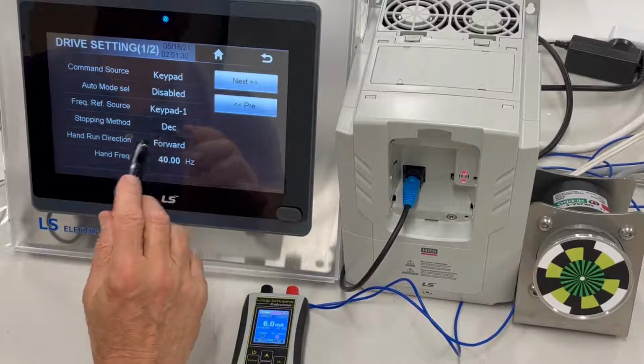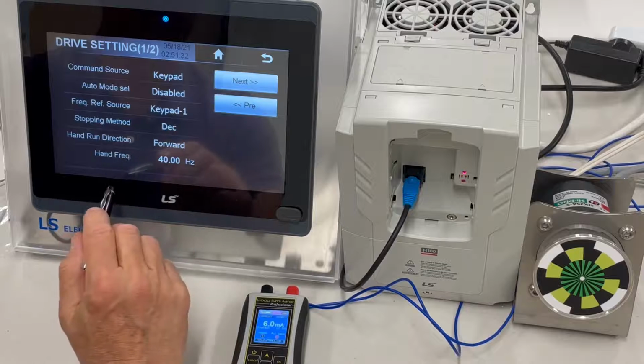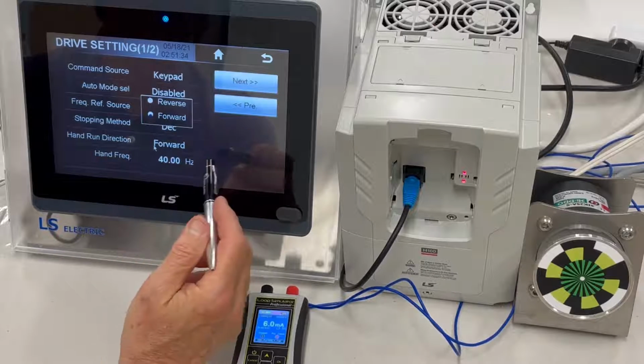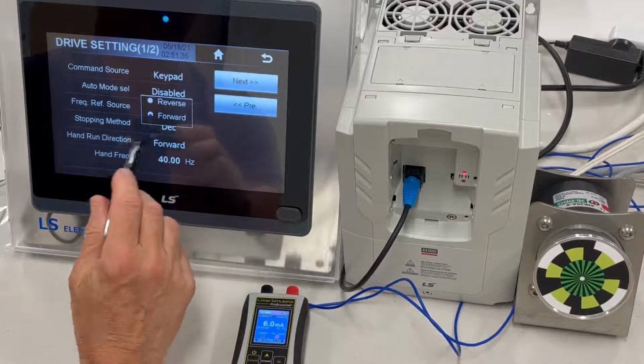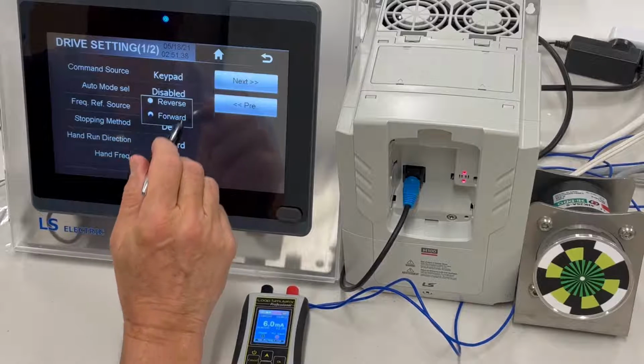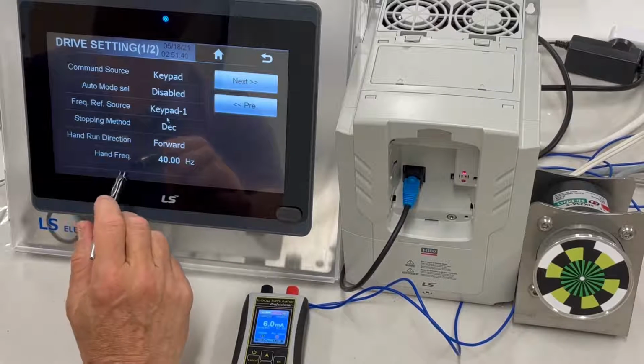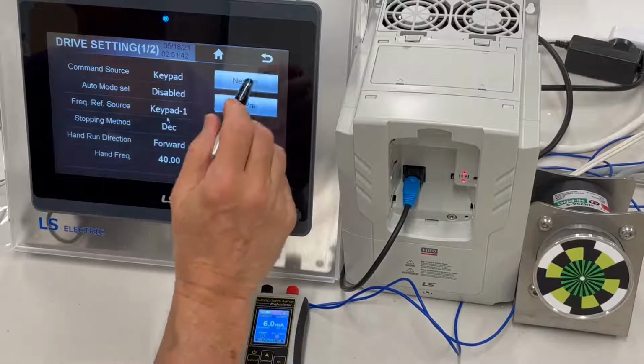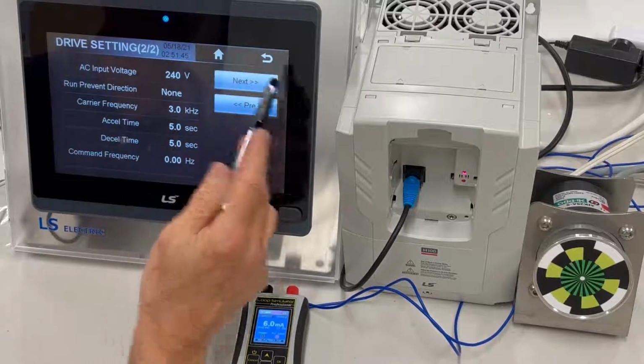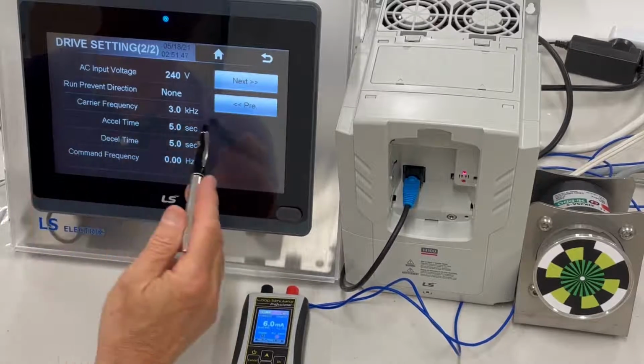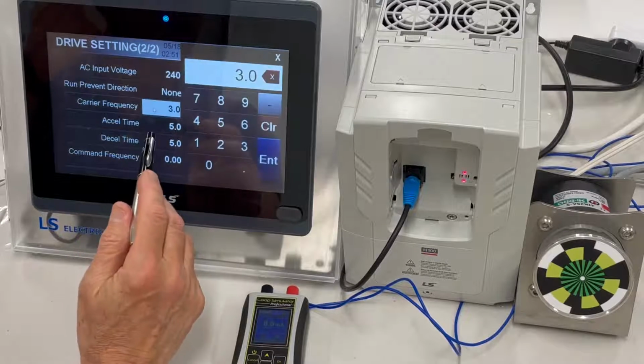So the stop method is decel, hand run direction is forward. Of course, you can change that. If you wire up your pump wrong, you can change that very easily. And we'll go from there. So we'll select forward, and hand frequency is 40 Hertz. AC input, there's on the drive settings. We basically have a 3 kilohertz carrier frequency.